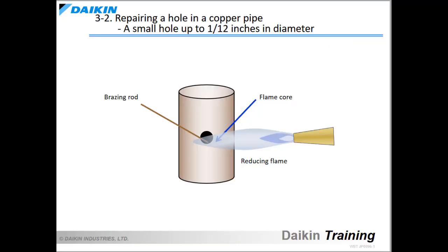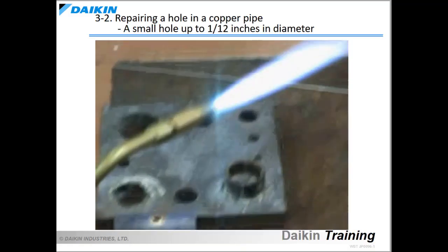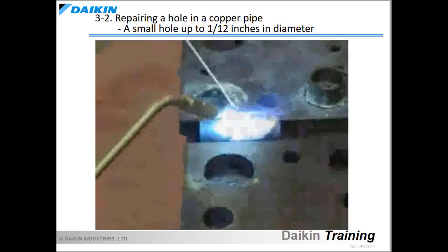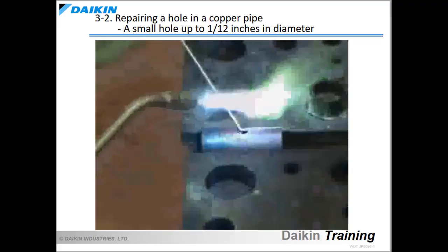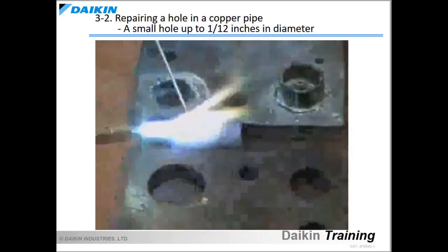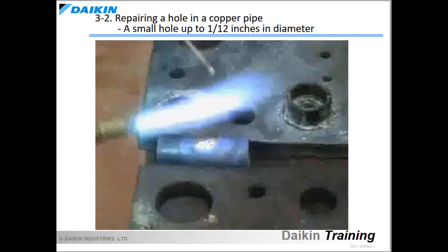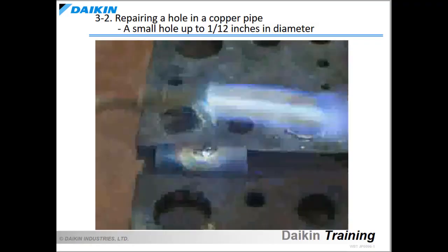Next, let's learn about the repairing method when there is a hole in the copper pipe. A hole smaller than 2 mm in diameter can be filled in with brazing filler metal. Use the reducing flame. Adjust the flame to a low intensity and melt and apply the brazing filler metal into the hole from outside in order to fill it in. Let's review the procedures for repairing a hole in the copper pipe in the video. In this case, use the reducing flame. Adjust the flame to a low intensity and melt and apply the brazing filler metal into the hole from outside in order to fill it in.